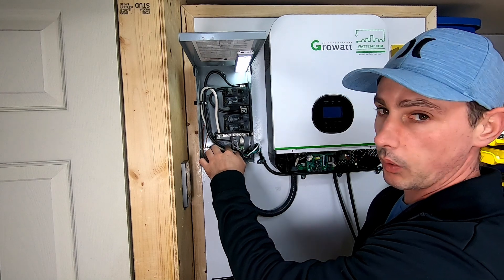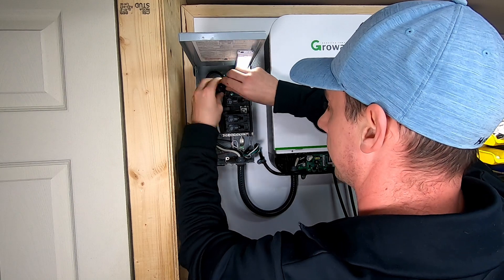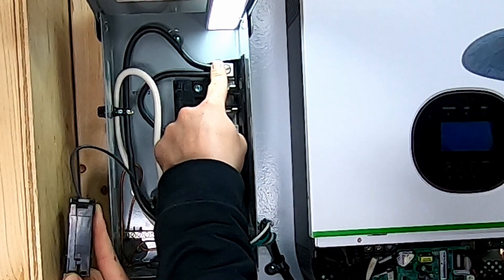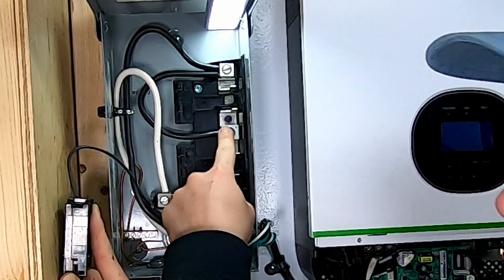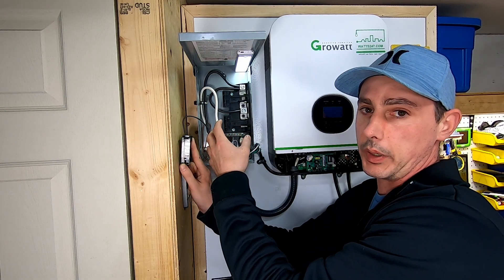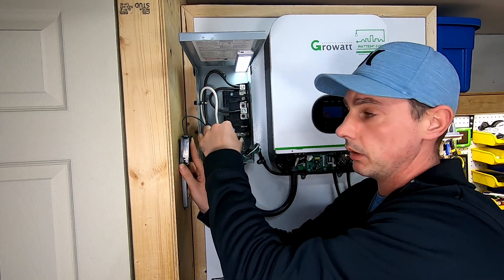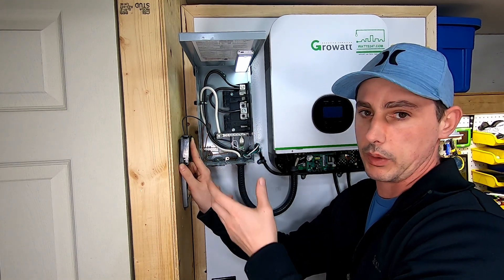My black wire comes in, runs up, and connects into the lug here, and then I have a jumper wire that runs it into the second lug over here. This is normally a 240-volt panel but the Growatt is only producing 120 volts, so I'm just livening both sides of the panel so I can have four breakers instead of just two with two empty slots.